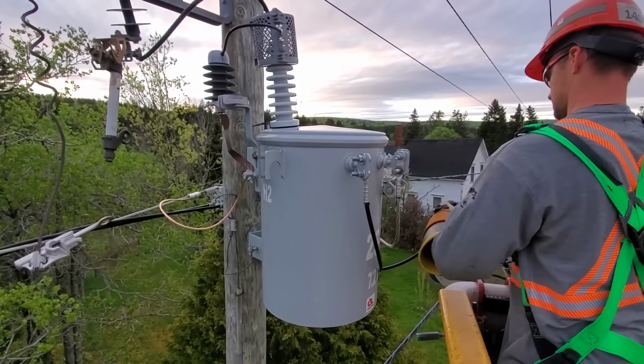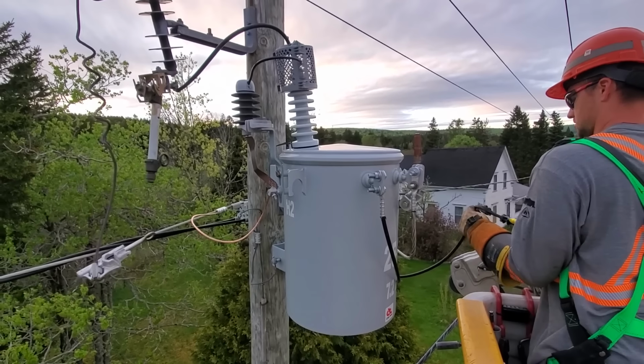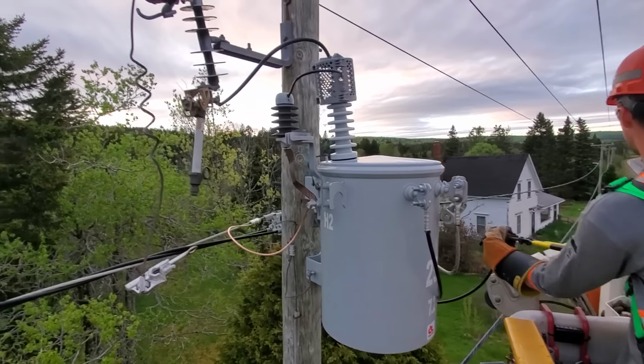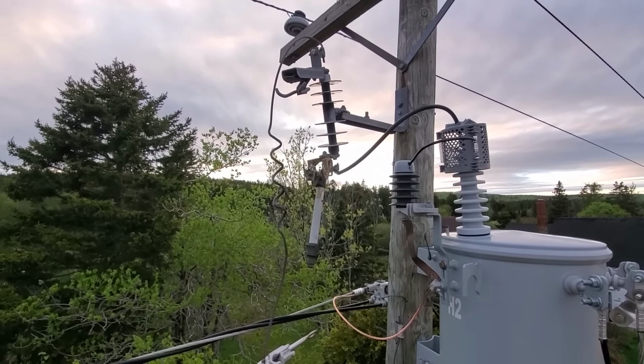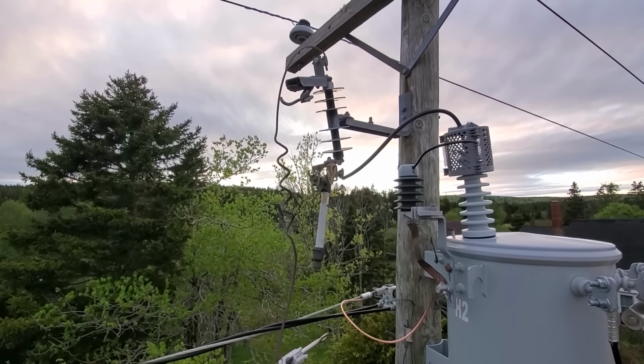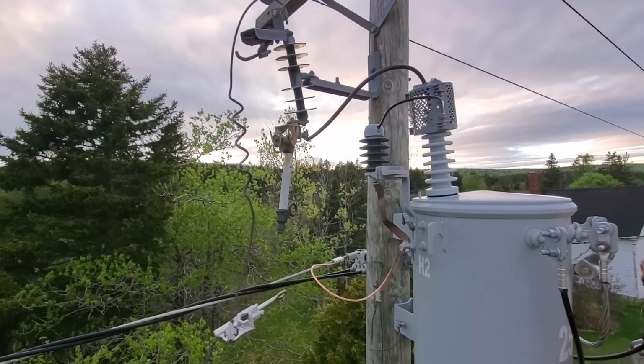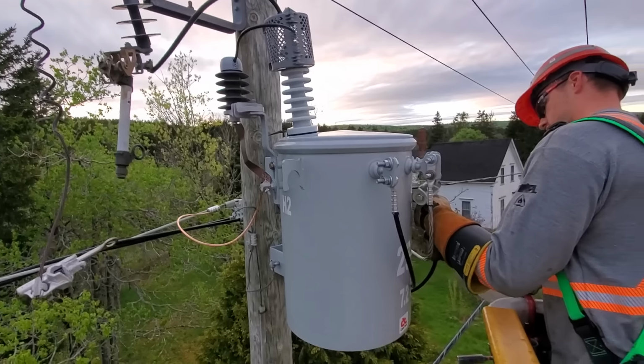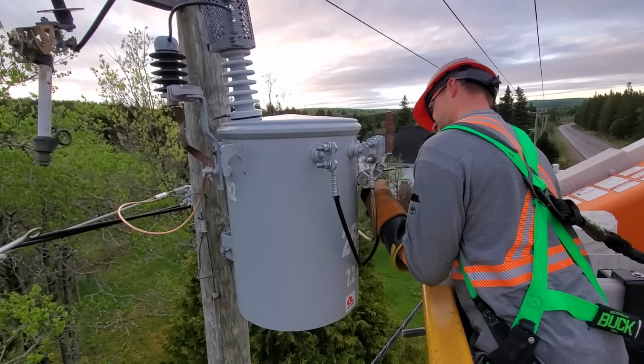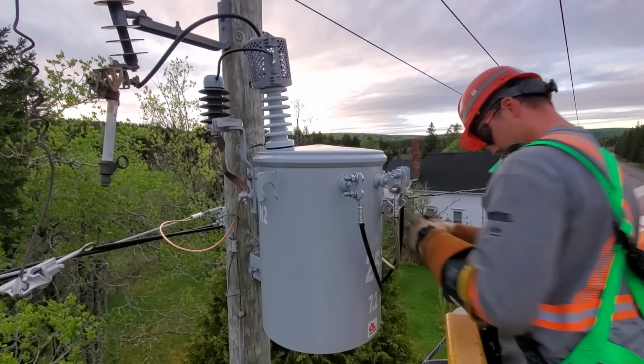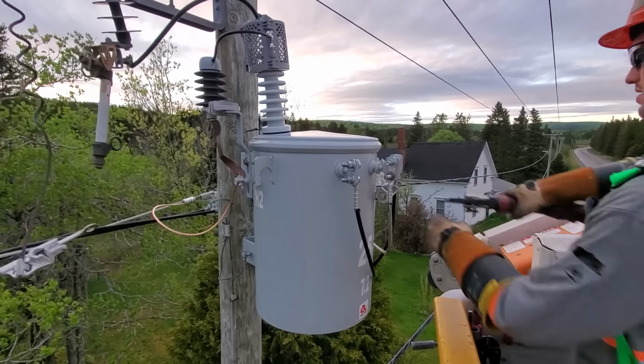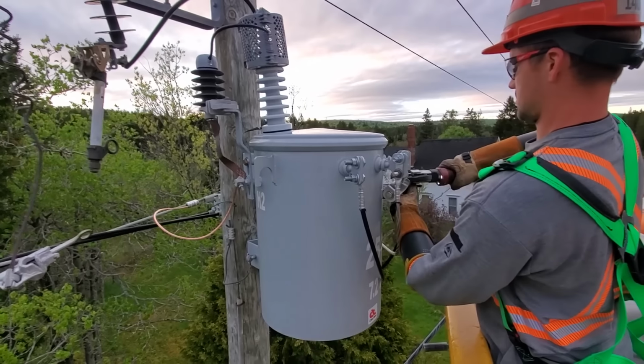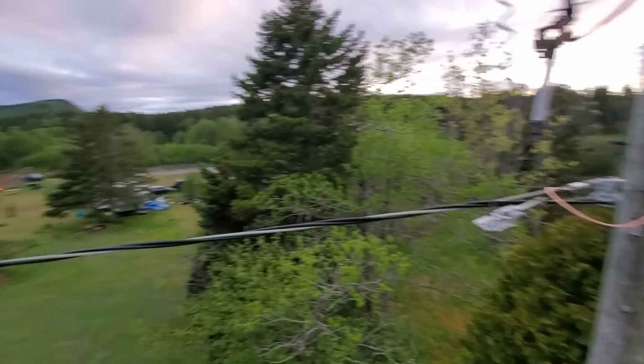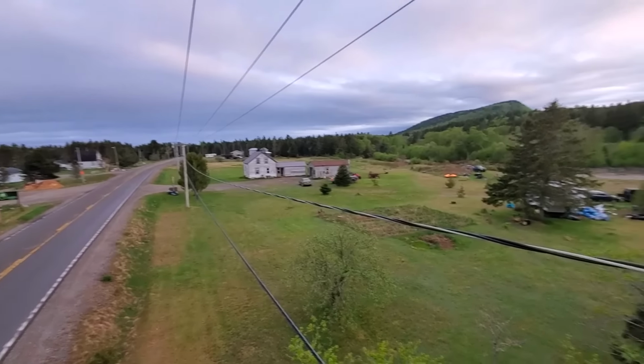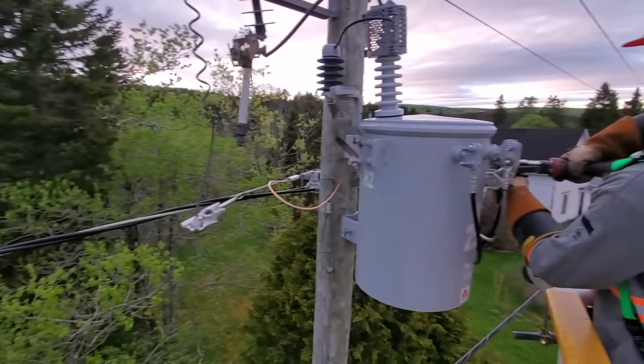A lot of times you hear people say a transformer blew when they hear the big bang and see the flash in the sky. That's typically just the fuse. They're loud and very bright. You don't want to be looking at it when they blow. In fact, even once this process is complete, when Ryan closes in that cutout, he's not going to be staring directly at it when he closes that door in, because we never know if maybe, even though we did inspect the rest of the line, that there isn't or wasn't another problem.